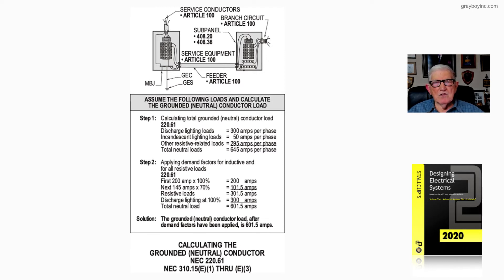In step one, we have electrical discharge lighting at 300 amps, incandescent at 50 amps, and other resistive loads at 295 amps. When we total those loads up, it's 645 amps.